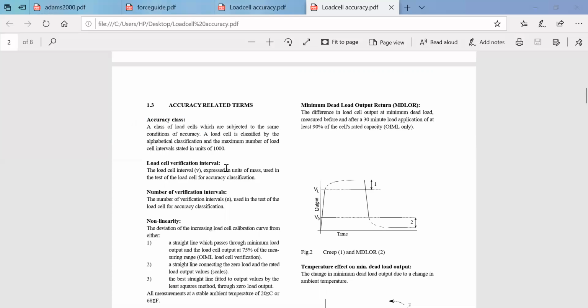So next is the load cell verification interval. What is this? The load cell verification interval is always expressed in units of mass, which is used in the test of the load cell for accuracy classification. In order to classify the accuracy, you should have some range of intervals for the load cell data which has been obtained. That is usually expressed in terms of mass, because you will apply the load and check what is the actual and the measured load you are getting. So basically the unit will be in terms of mass. You will bifurcate into different interval ranges so that you can classify the measured and the actual weights of different slotted weights that you compare using a load cell.